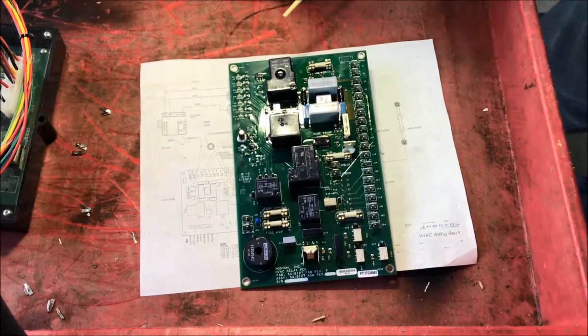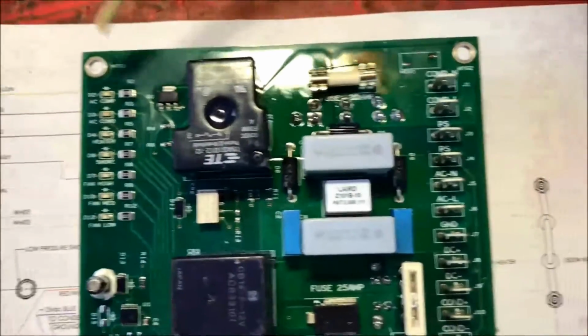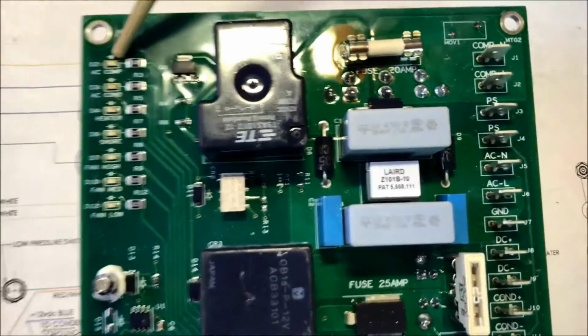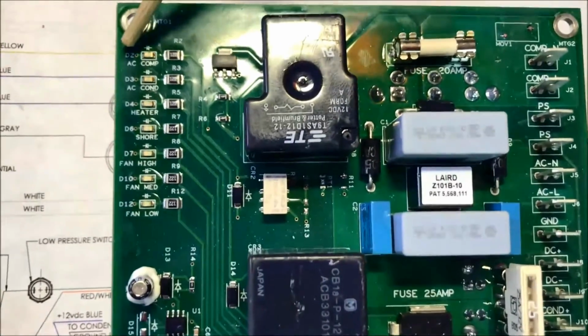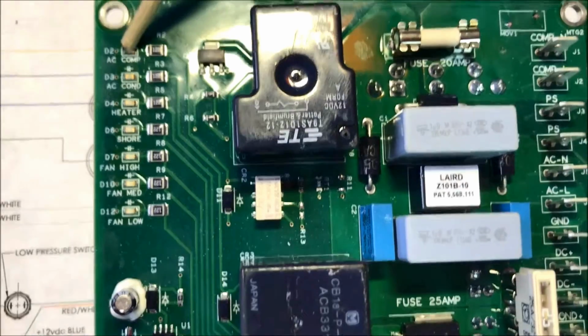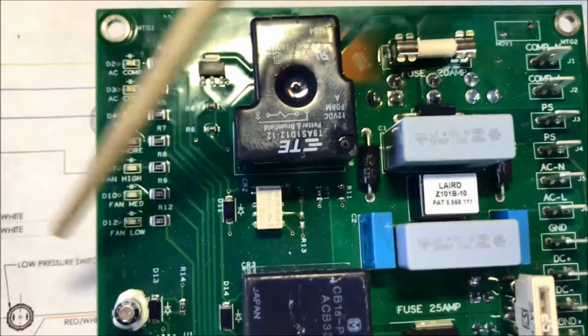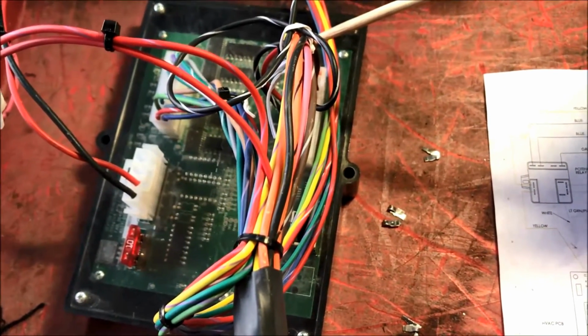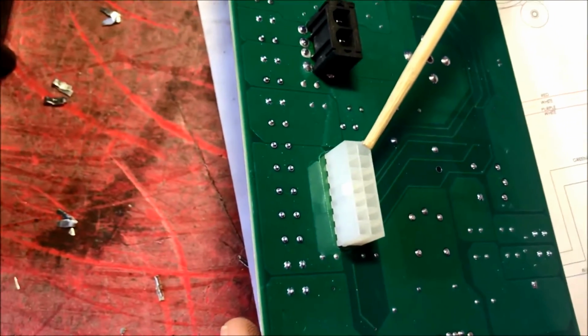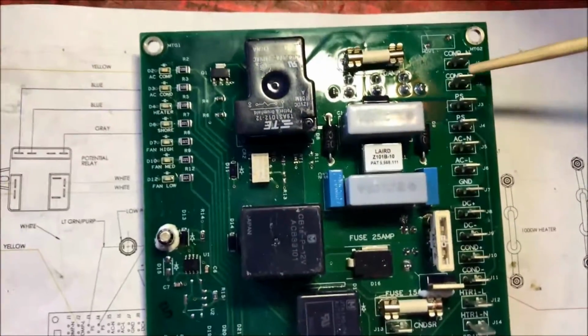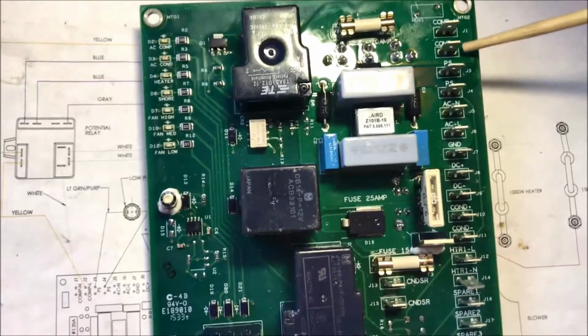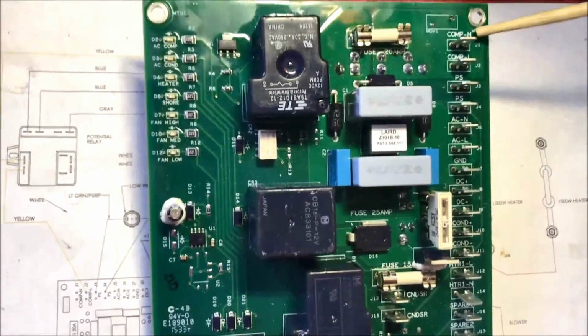And this is the back side of the circuit board. It's facing the compressor. We have it down here to show you what's going on. One of the interesting things is that this row here is LED lights. When you have the AC compressor activated, this light should be on. What this light will say is that the DC signal from the controller is asking the HVAC to turn on the AC compressor with a 12 volt DC signal on this side. Then the relays will close, this light will activate, it will conduct 120 volts through the relays, and the power will come out here.